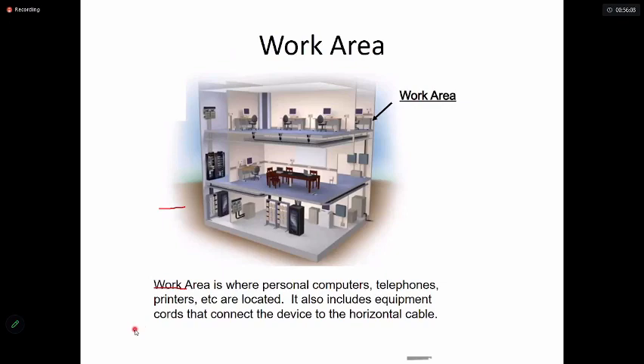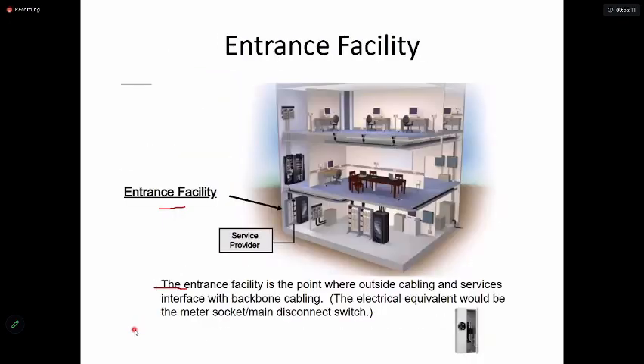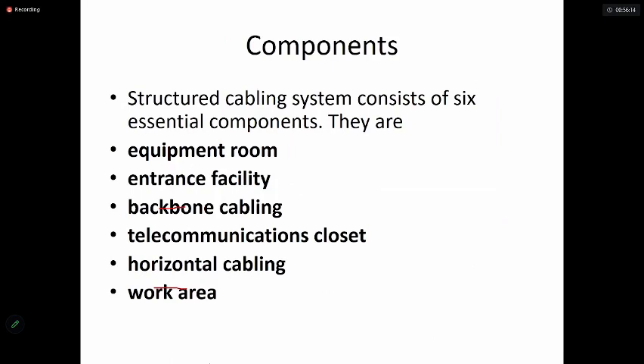Everywhere there is a connection, we use a patch panel, and there are 6 components involved. Whenever you install or design this kind of ELV system, you have to arrange everything accordingly: the central equipment is at the equipment room, and incoming cables and the service provider's equipment are at the entrance facility. From the equipment room to the floors, there is backbone cabling. At each floor, all the equipment needed is kept at the telecommunication closet, then through patch panels there is horizontal cabling, and from the horizontal cabling we make connections from the telecommunication closet to the work area.